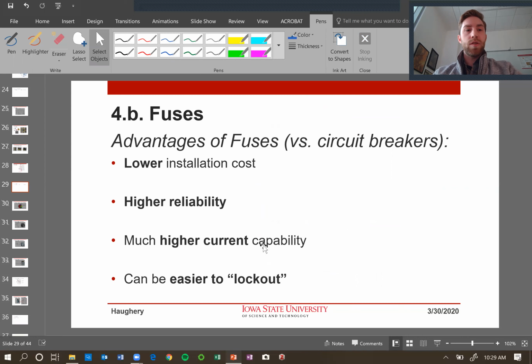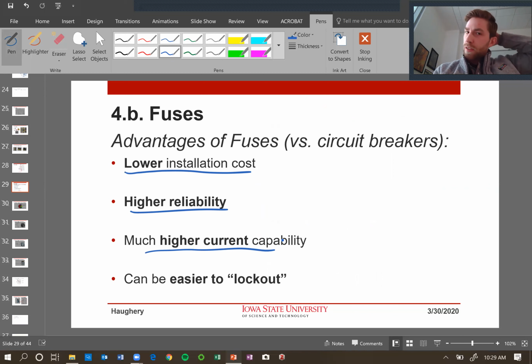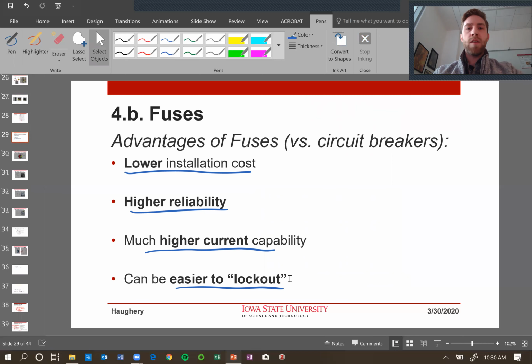Advantages and disadvantages of fuses versus circuit breakers. A fuse usually has a lower installation cost. Fuses are oftentimes higher reliability, so a lot of times sensitive electronics have fusing, not a circuit breaker, for protection locally. There's a higher current capability for fuses, and a lot of times it's a little bit easier to lock out the fuse. You just pull it out and then it's not there. If it's in your pocket, it's harder to put back in, or if it's in a locked box with your lock and tag, then it's harder to put back in. You can't cut the locking mechanism off of a fuse if the fuse is not even there.